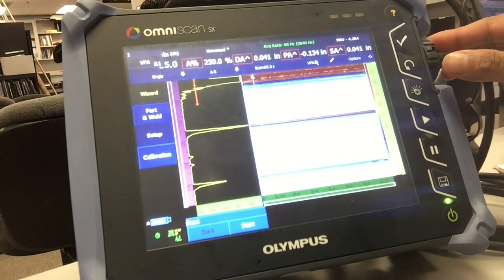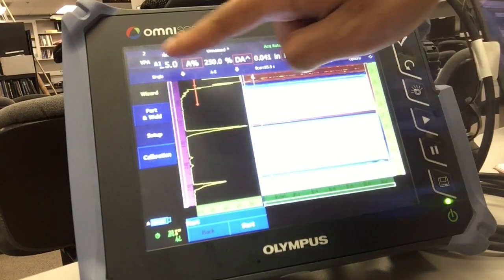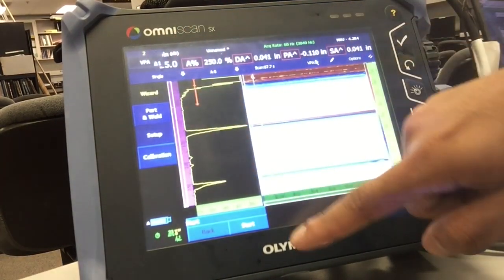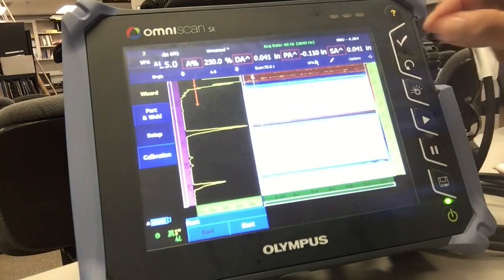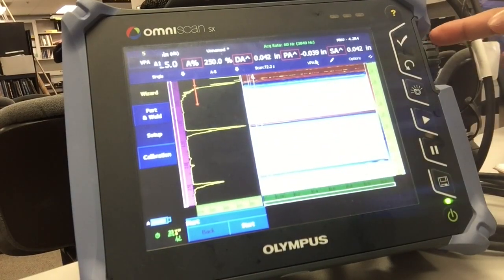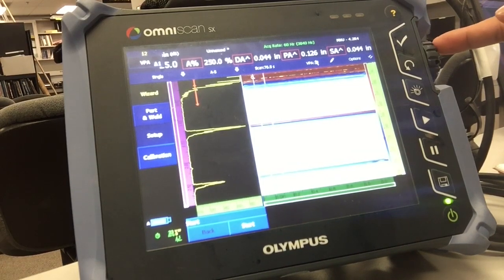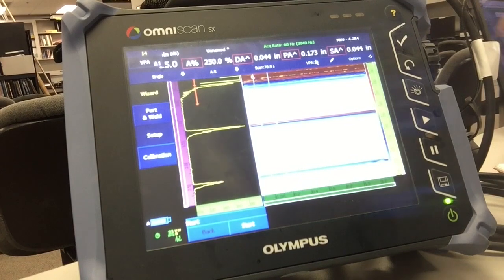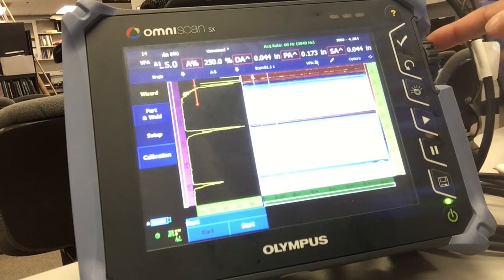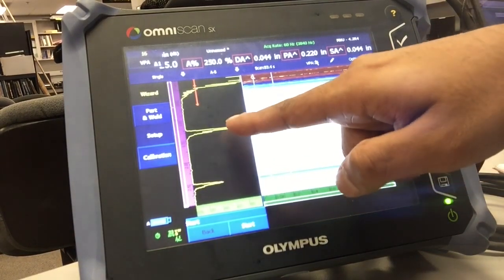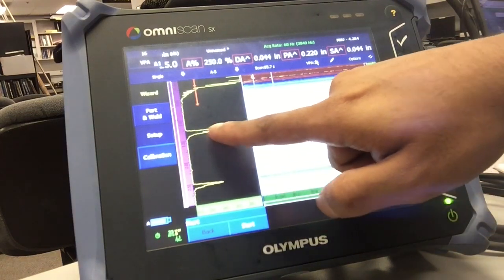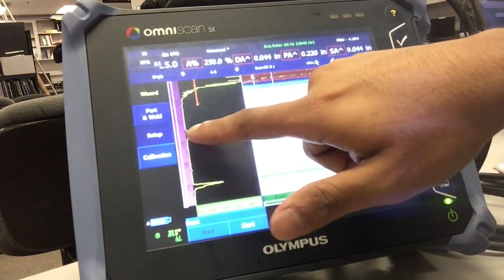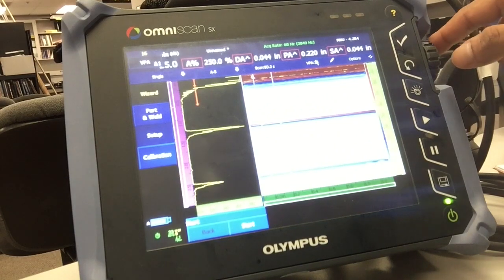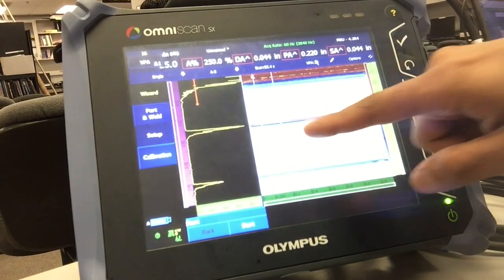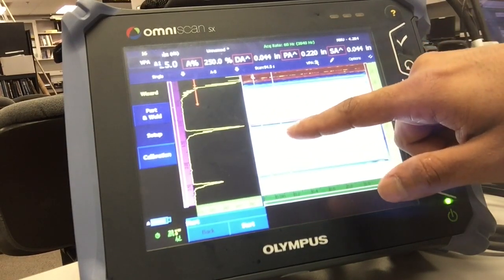As I scroll to VPA 2, now the A-scan signal that you see on the screen is from the second element in your crystal. And so on and so forth. As I scroll through my VPAs, it is scrolling through each and every element at a time and giving you the corresponding A-scan signal for that particular element. So I'm going to watch my A-scan signal to drop down. If it drops down, then I have a dead element. If it doesn't, if it stays in the range of somewhere around 90 to 100%, then it's a good element.